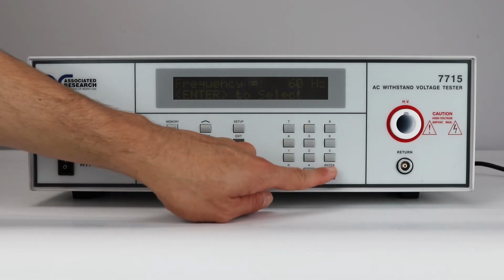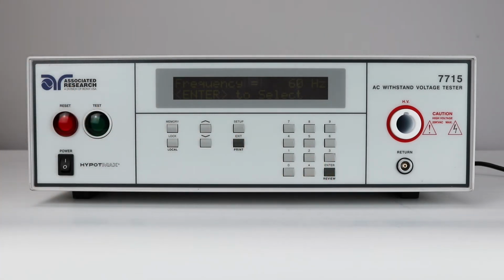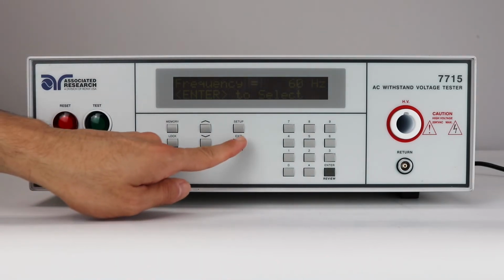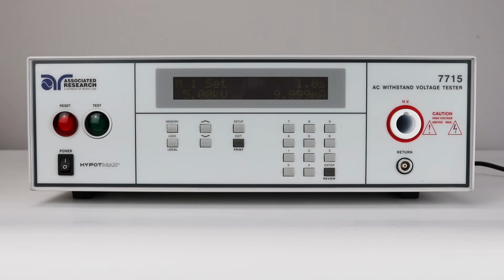the values. For the purposes of this video, the Hypot test will be set to 5000 volts at 60 Hz with a 2-second dwell time. After all the parameters have been adjusted, press the Exit key to return to the Perform Test screen. Finally, we're going to show you how to connect the HypotMAX to a DUT and run the test sequence.